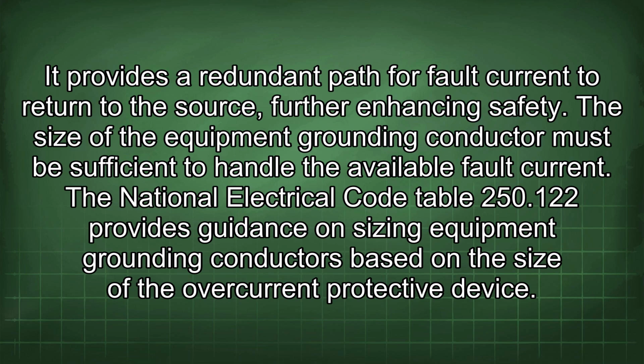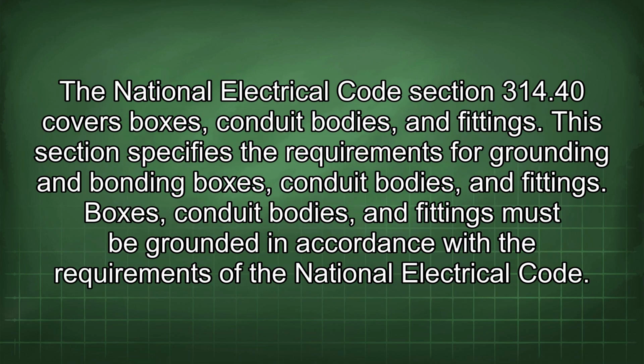The National Electrical Code Table 250.122 provides guidance on sizing equipment grounding conductors based on the size of the overcurrent protective device. The National Electrical Code Section 314.40 covers boxes, conduit bodies, and fittings. This section specifies the requirements for grounding and bonding boxes, conduit bodies, and fittings. Boxes, conduit bodies, and fittings must be grounded in accordance with the requirements of the National Electrical Code.